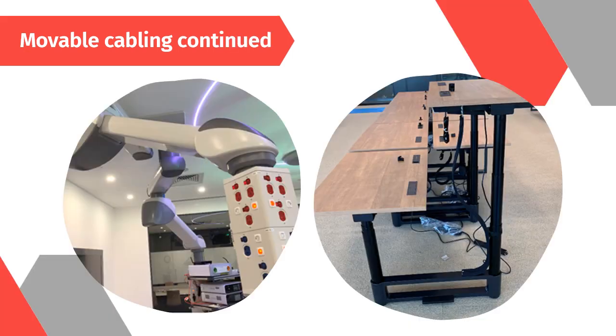The most common usage for movable cabling that we see in Australia are in the case of sit-stand desks and pendants. Pendants are mostly found in hospital environments. In these two scenarios, a cable is typically terminated at an outlet which is fixed to the desk or at the bottom of the pendant with other outlets such as nurse call or oxygen, etc. These cables have the possibility of moving multiple times a day, and without the use of stranded cable, they would not be able to withstand the bends and twists that happen in these situations. Remember, derating formulae must be applied when using stranded cables and patch cords.